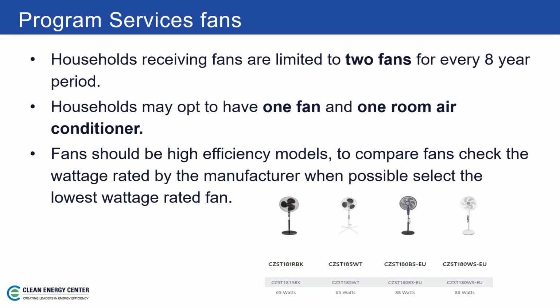So just in the illustration below, these are all 18-inch fans, but you can see we're looking at the wattage consumption there, and the watts is how we measure power, and that's how you're going to be billed. So you can see that there are two fans there that are 65 watts each, and there are two fans that are 88 watts. Now, the two fans on the right may move more air, I don't know, but just try to be a little bit cognizant of that whenever you're selecting fans, whatever type of fan you're going to get for your client. Research a little bit, and you want to get the ones that consume the least amount of wattage. So it is in the pilot that the fans should be high efficiency models.